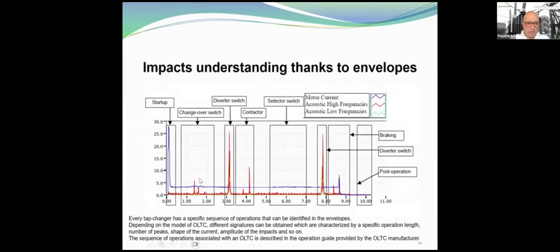Every tap changer has a specific sequence of operations that can be identified in the envelopes. And depending on the model of OLTC, different signatures can be obtained, which are characterized by specific operation length, number of peaks, shape of current, amplitude of the impacts, and so on. And the sequence of operations associated with an OLTC is described in the operation guide provided by the OLTC manufacturer.